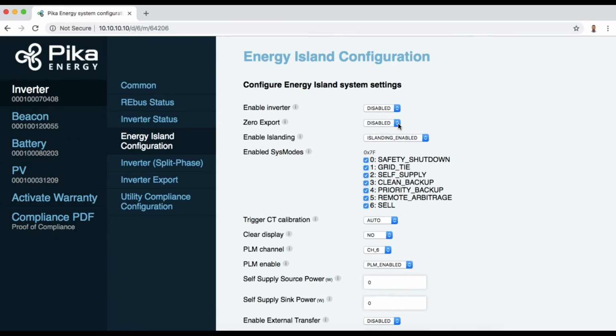As an example for this video, I'm going to pretend as though we are configuring a system for Hawaii Rule 14H1. So after I have the inverter disabled, the first step is to enable zero export, assuming that we have already calibrated our CTs. Our current transformers are used to measure consumption of the house. So if your inverter is already showing a utility pole on the bottom right of the LCD screen at the main power flow screen, then you're all set.